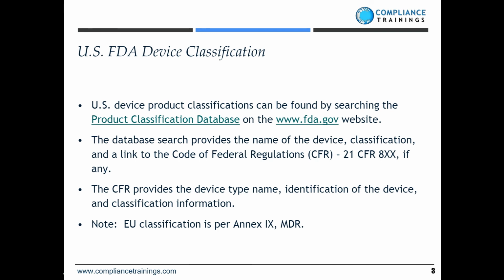If you're going to sell outside the United States, then you have the Medical Device Directive currently and the Medical Device Regulation, which is being phased in. You have CE marking. You have ISO 13485 for your quality management system, and you work through a notified body. But what we're focusing on here is working with the GMPs, 820 for devices, and the various submission routes through the FDA for sale of product in the United States. So that's our focus in this discussion.